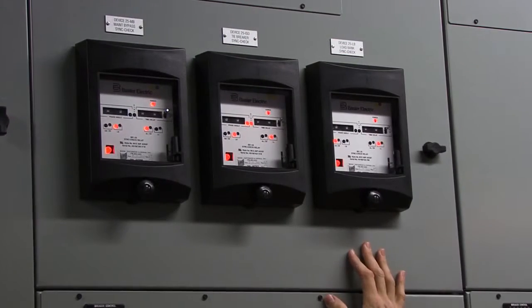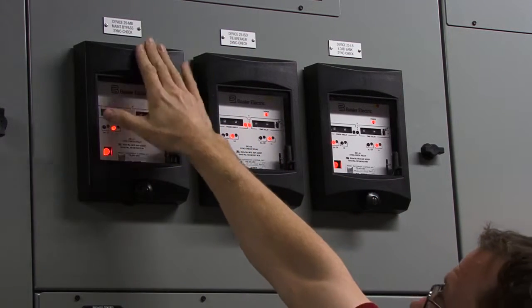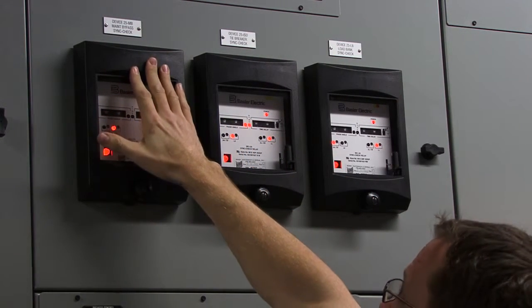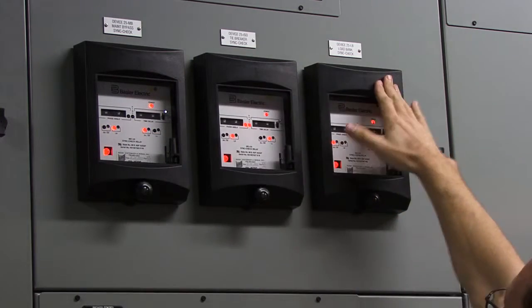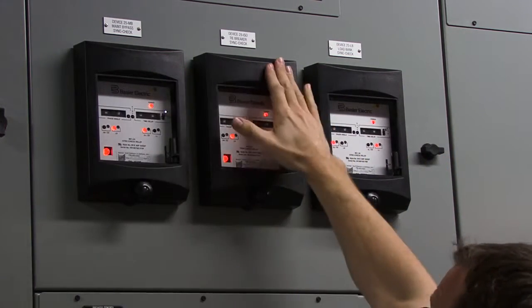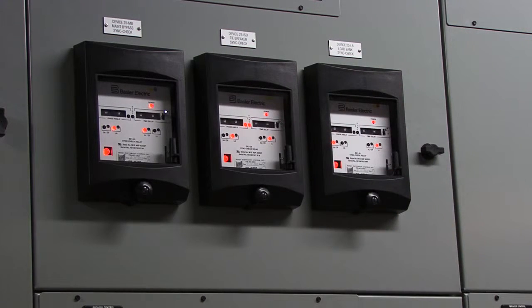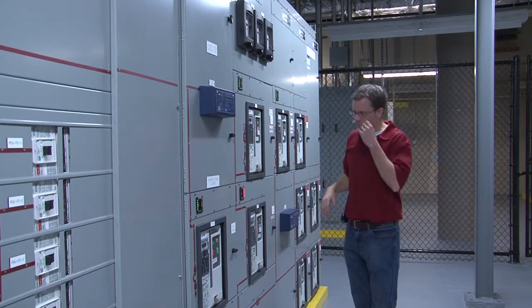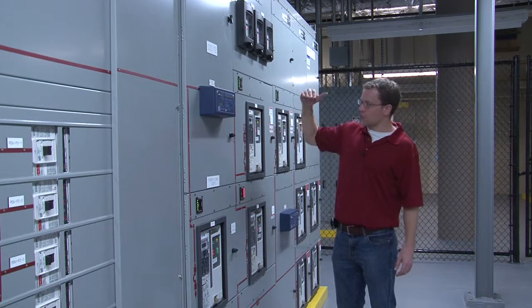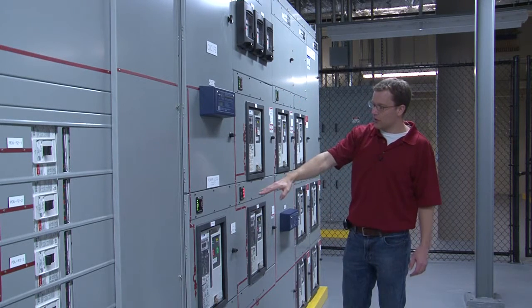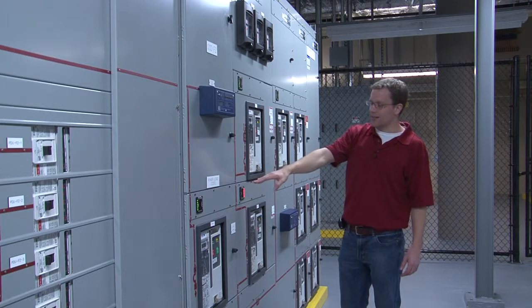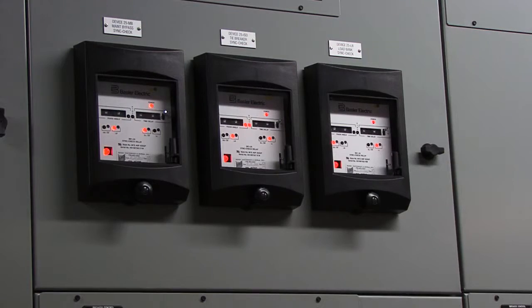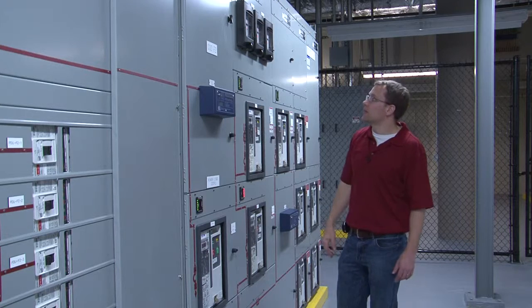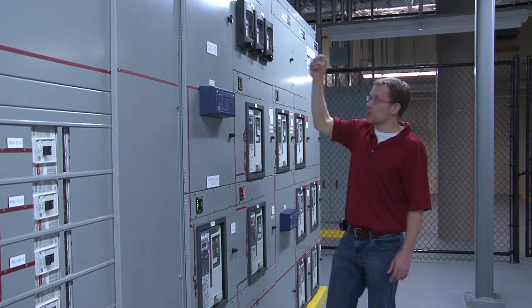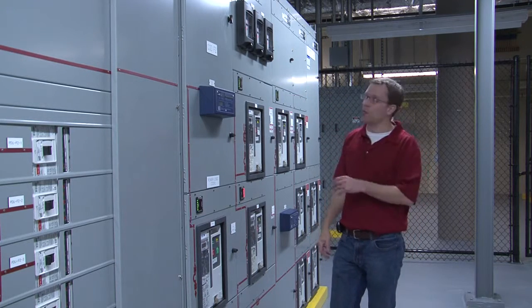Up here we have 3 sync check relays. Each relay looks across a different breaker. So device 25-MB, ISO, and LB refer to the maintenance bypass breaker, the isolation breaker, and the load bank breaker. So in each case, the sync check relay is looking from the source side of the breaker, which is called the line, and the bus side of the breaker, which is the load side. And it indicates live line and live bus just like it did at the UPS input substation. Just like the UPS input substation, you can take these out, slide them out, put a new one in.